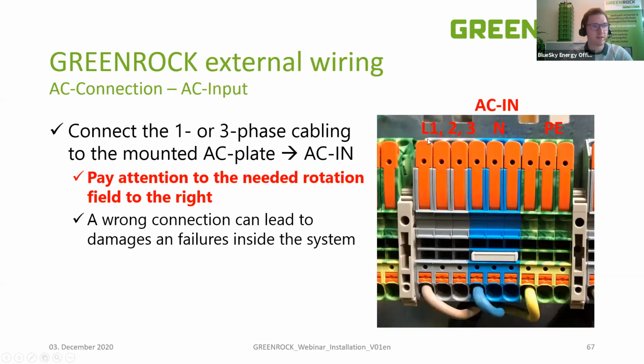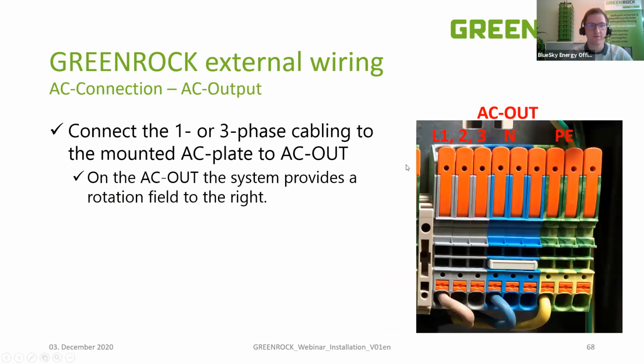So on the AC in, please just place the cables on the top. These are really toolless AC connections. Please be aware, if you have a 3-phase system, that you need the correct rotation, so the correct rotation of each phase to the other. In this case, we just talk about a rotation field to the right. So really important if you have a 3-phase system. Also the AC out, a 3-phase GreenRock system is providing a phase rotation to the right direction. I have to show it in a different way inside the camera.